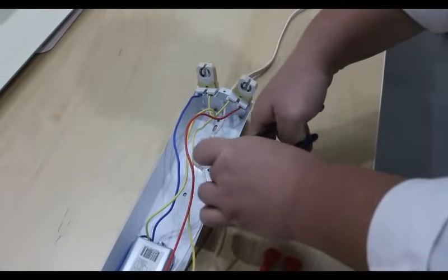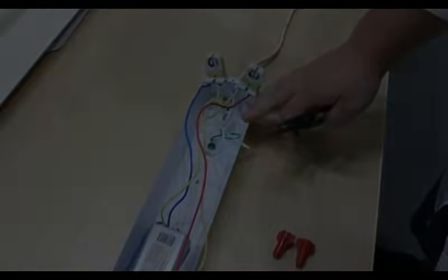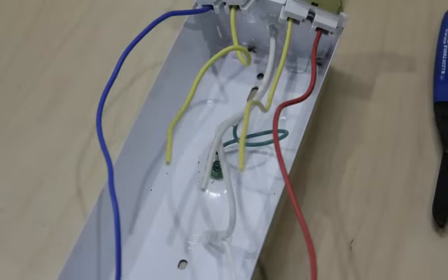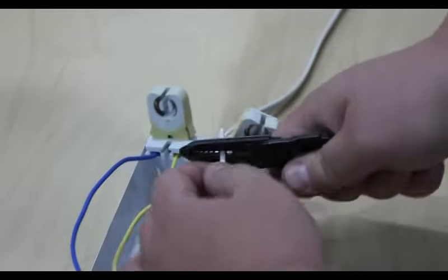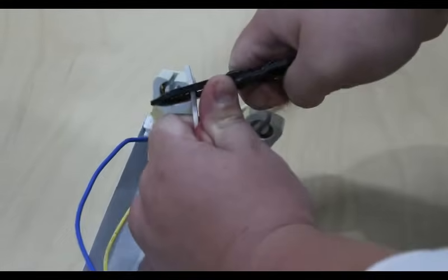Clip the hot or live wire and the yellow wires which are just on one side of each of the two lamp plugs. You are only wiring one side of the fluorescent lamps since Star LED ballast bypass LED tube lights get their power from one side.